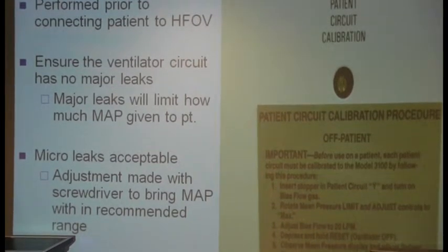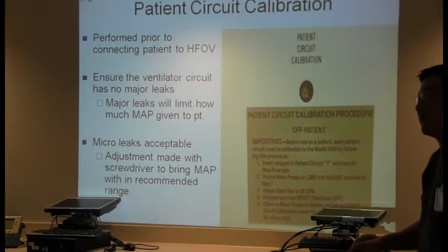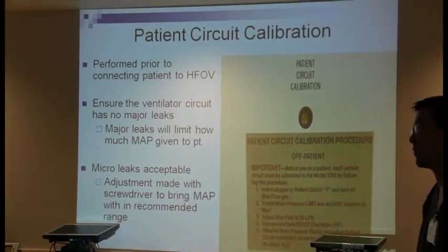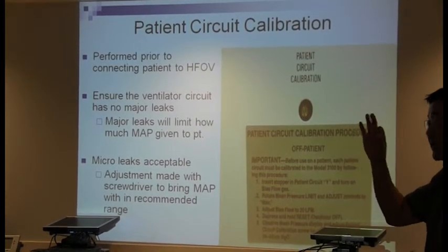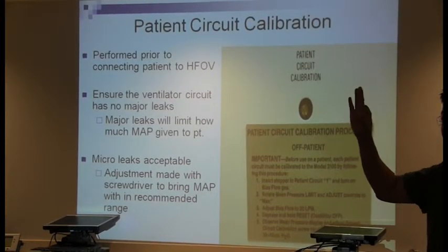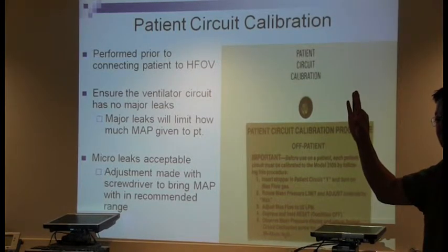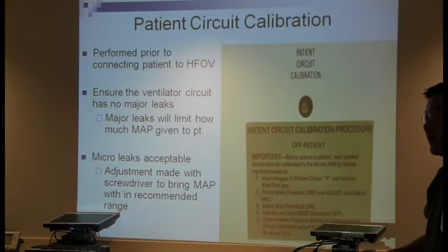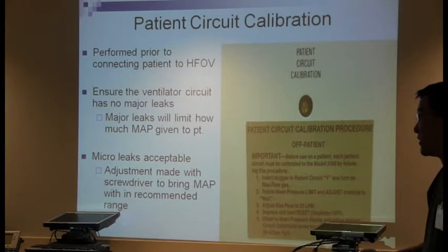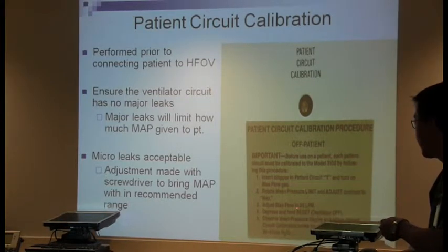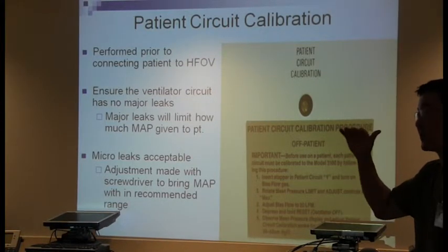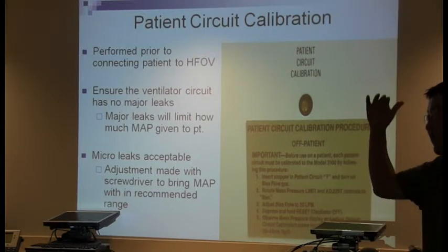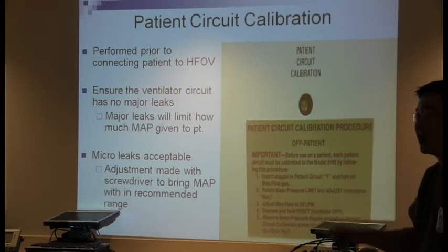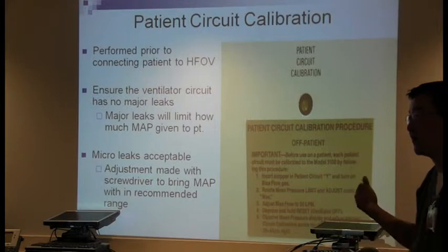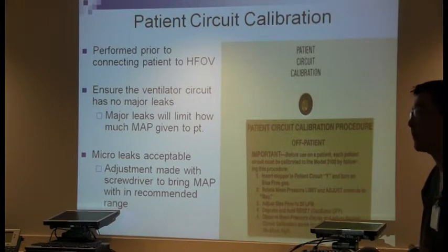The other part: your bias flow needs to be at 20. And remember, what's more correct when we adjust the flow meter is that the ball needs to be in the middle of the line, not above or below it. That's how we set our settings. So when we set our bias flow, it needs to be at 20 liters at the middle line. If it's below, that means you don't have enough bias flow going through. So that's why your mean is not 39 to 43.